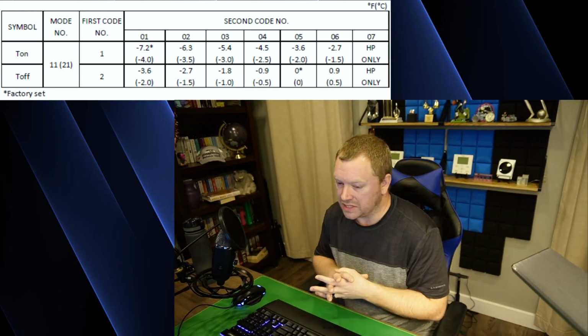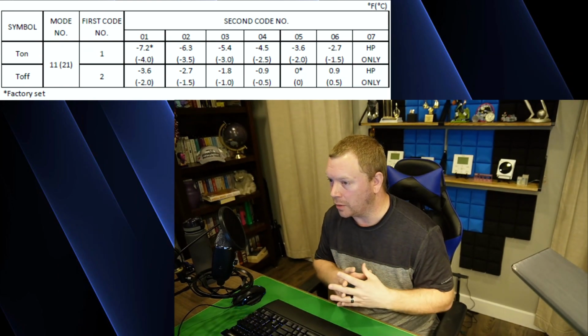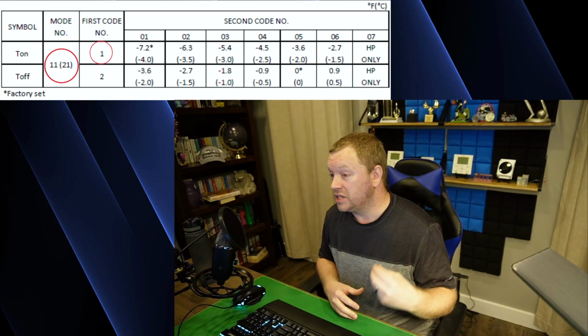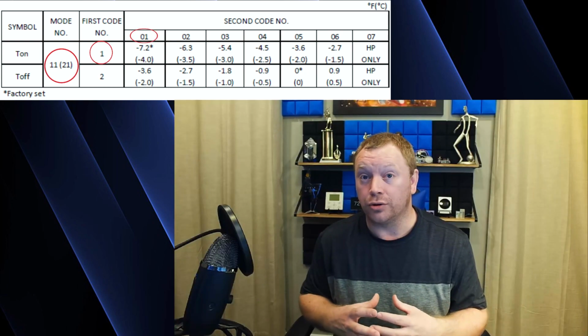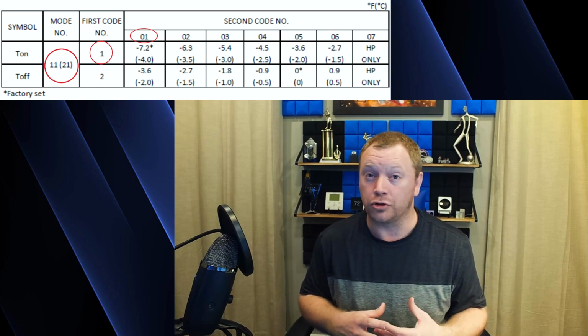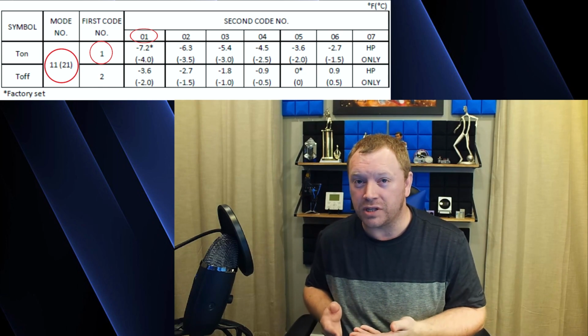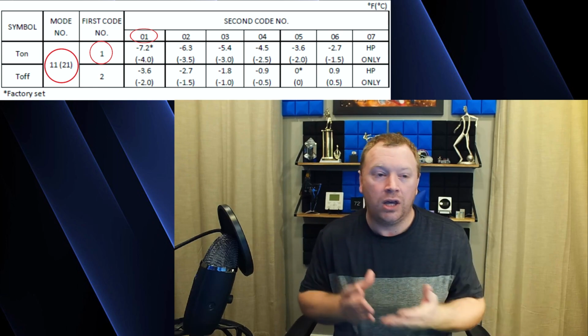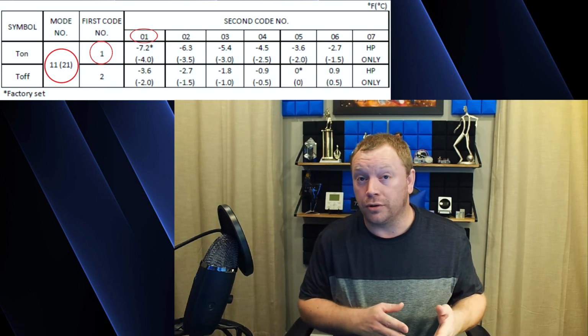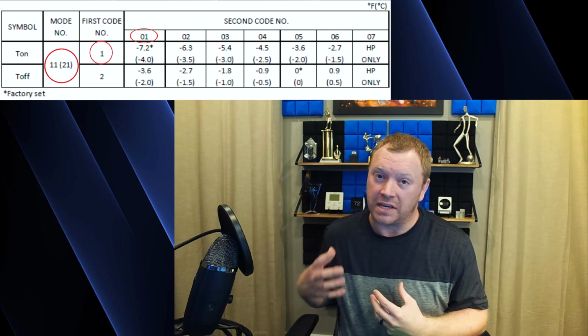So in this case, because you can't run the gas furnace with the heat pump, it's at what temperature do you want the room to fall below the set point before it kicks on the gas for the heat pump. So it shuts down the heat pump, turns on the gas. So your default in this case is the same as with your strip heat options. Mode 21 setting 1-01 is 7.2 degrees below your set point. It's how far your room temperature can drop or droop. I like to call it the droop temperature because your room temperature is drooping below the set point. 7.2 degrees before it kicks on the gas and shuts off the heat pump in this case.